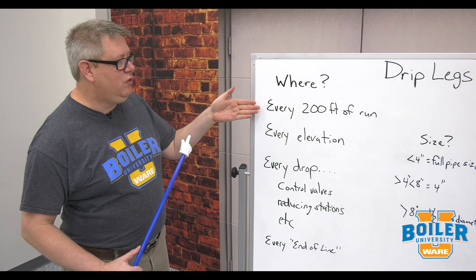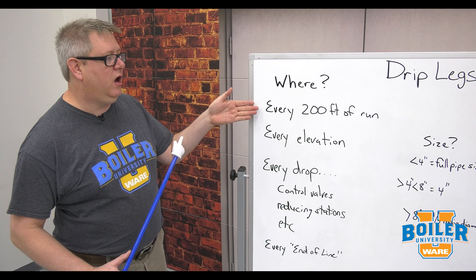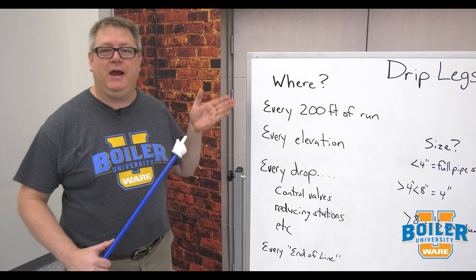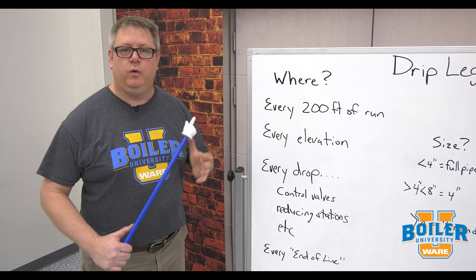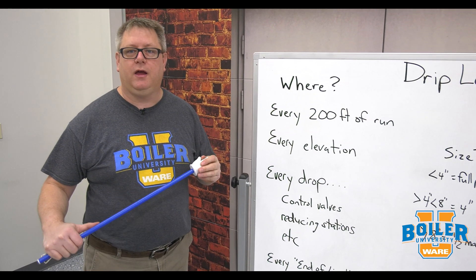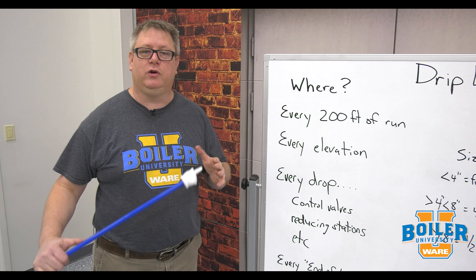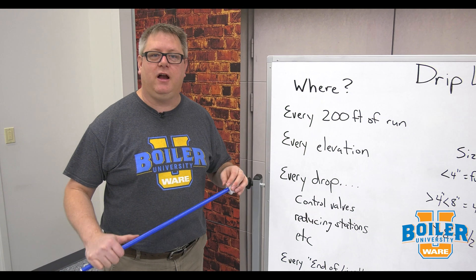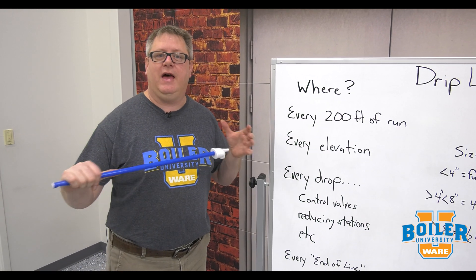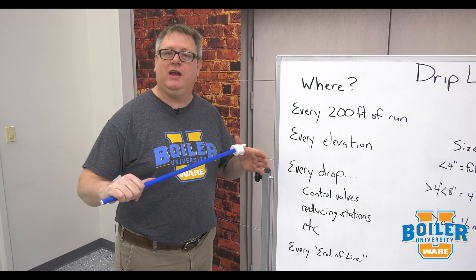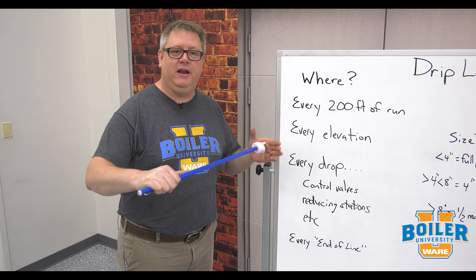First, every 200 feet of steam main run we want a drip leg, and that's because we're generating condensate in that run and we need to get rid of it at intervals.